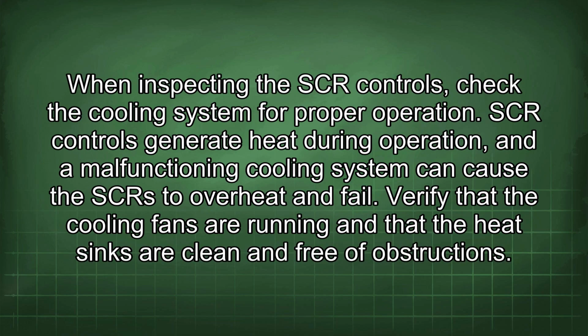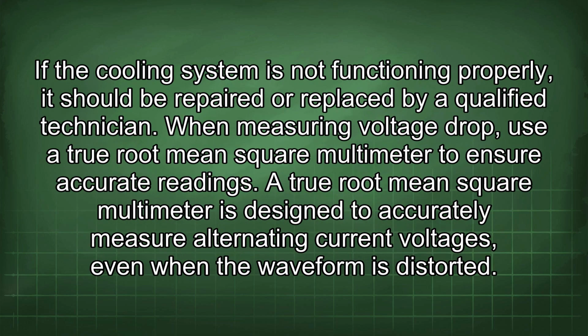When inspecting the SCR controls, check the cooling system for proper operation. SCR controls generate heat during operation, and a malfunctioning cooling system can cause the SCR to overheat and fail. Verify that the cooling fans are running and that the heat sinks are clean and free of obstructions. If the cooling system is not functioning properly, it should be repaired or replaced by a qualified technician.